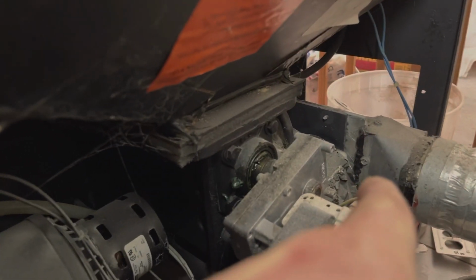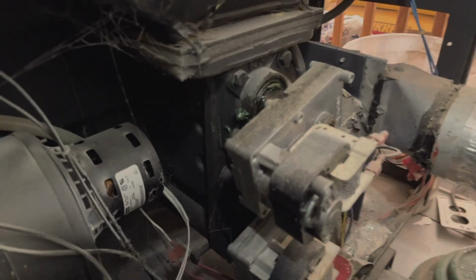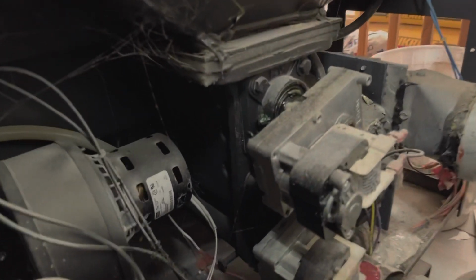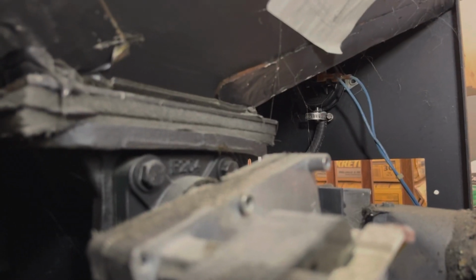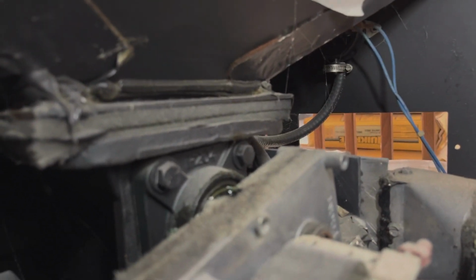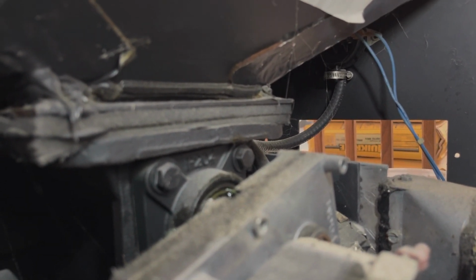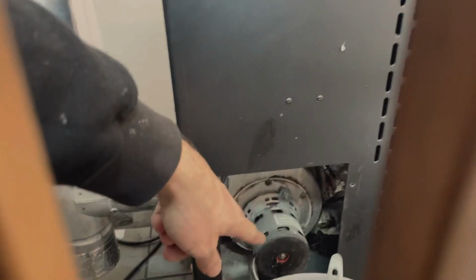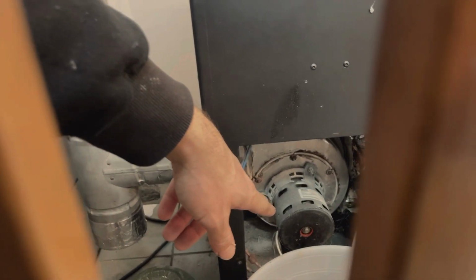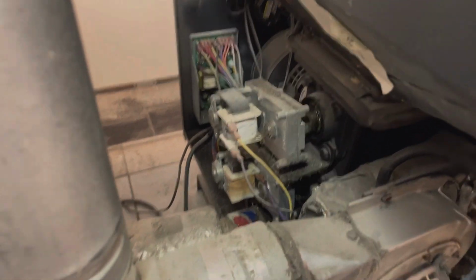Once you know how to work on your furnace, you can learn how to work on this. Similar, there's a control board, there's a blower motor, there's an inducer motor or exhaust motor that runs that on the other side. One thing that's different is there's gears, and you got to grease the gears there. But similarly, there's a pressure switch, like in a furnace. On the other side, there's another pressure switch, the hoses. I think I had an issue where my hose was bad, so I replaced that hose, you can see. And a maintenance thing with them is to replace gaskets on them. There's the inducer motor, and you can see those parts are very similar to a furnace. So learning to work on one thing correlates to working on another.